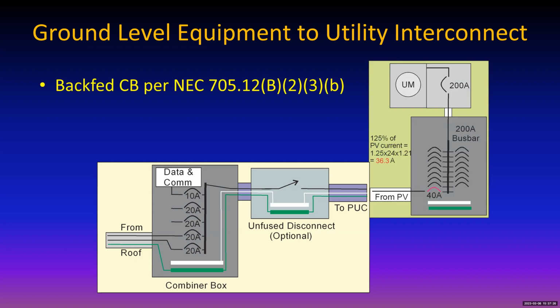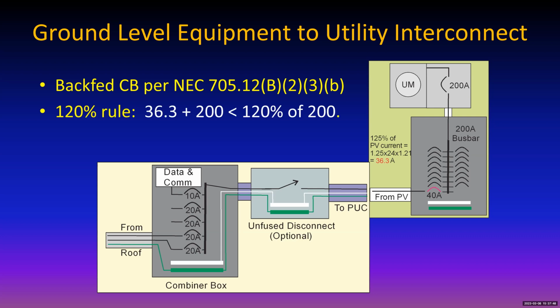How are we going to do that? Well, one way to do it is to connect it by means of a backfed circuit breaker, according to NEC 705.12(B)(2)(3)(b). I don't know how many times I've said that because we talk about it all the time. It's one of our favorite topics at work. Point is, it's called the 120% rule.